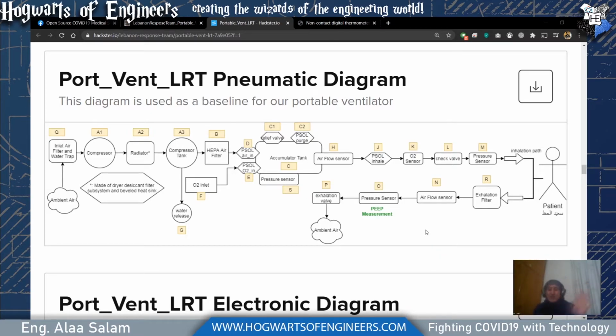That's why it's always good to test your breathing circuit before you use it on a patient, because it's very hard to locate and compensate for a leakage when it's placed on a patient than when you're testing it in regular test mode. So that's why we also have in our ventilator design a stage where you test your ventilator every step of the way.